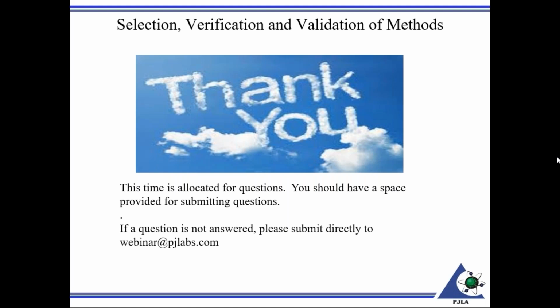If you happen to go to an unaccredited provider, and I don't want to go too much off base here, we do have protocol, and you can review this in our PL2 on traceability for non-accredited sources. The thing with that is you have some additional hoops to jump through. In PL2 we talk about the 7 elements of traceability. Typically, as calibration program manager, I get these requests and I look for additional objective evidence. Like I mentioned, measurements would not be considered traceable without a measurement uncertainty.